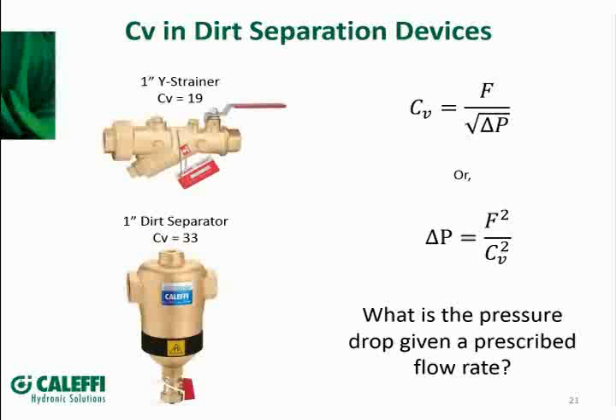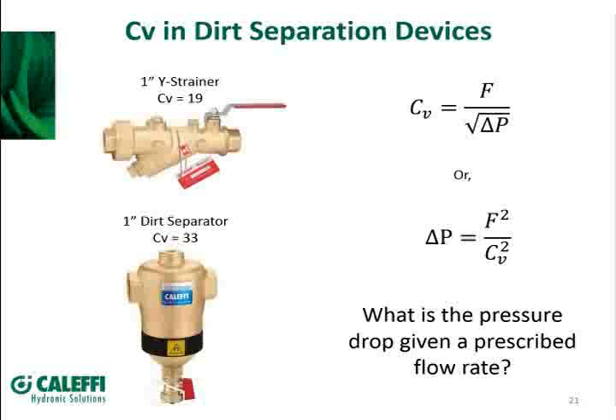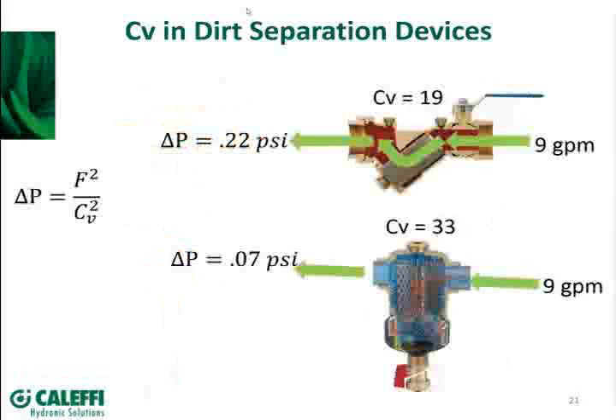We had a couple of questions coming in about glycol-based systems or water temperature other than 60 degrees Fahrenheit. The equations shown here assume basically straight water at approximately 60 degrees. If you have glycol or water at a significantly different temperature than 60 degrees, the more complicated formula is used that takes density into consideration. The density of glycol-based systems is different than water, and the density of water at 150 degrees Fahrenheit is different than at 60 degrees. We do have a slide later that clarifies using a different type of fluid other than water.